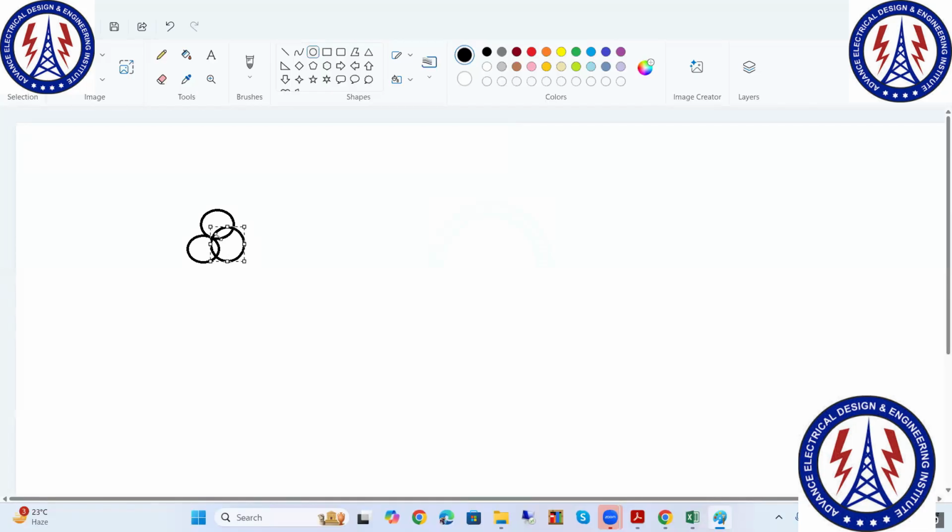In the second, once again R is on top, here Y and B, then B and Y will be interchanged. The cable will be interchanged. This is my first run, this is my second run. The spacing will be 2D. Accordingly, you will use 13 runs: 1, 2, 3, 4, 5, 6, 7, 8, 9, 10, 11.